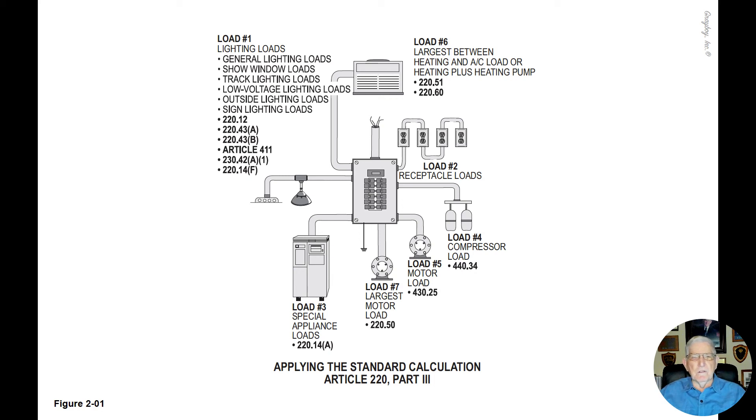This illustration deals with applying the standard calculation. Load one consists of the lighting loads. As you see in the illustration on the left-hand side top, the lighting loads consist of general lighting load, show window loads, track lighting loads, low voltage lighting loads, outside lighting loads, and sign lighting loads.